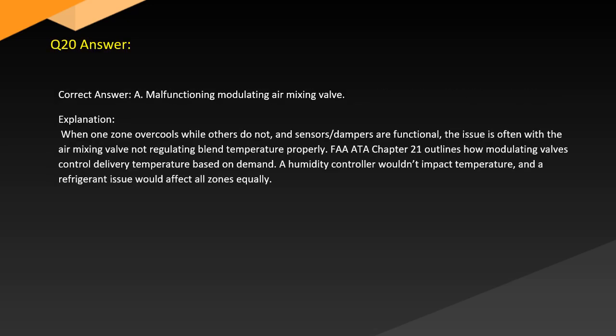Answer. Correct answer A. Malfunctioning modulating air mixing valve. Explanation. When one zone overcools while others do not and sensors and dampers are functional, the issue is often with the air mixing valve not regulating blend temperature properly. FAA ATA Chapter 21 outlines how modulating valves control delivery temperature based on demand. A humidity controller wouldn't impact temperature, and a refrigerant issue would affect all zones equally.